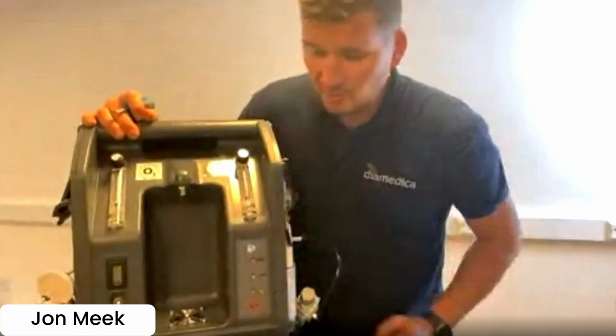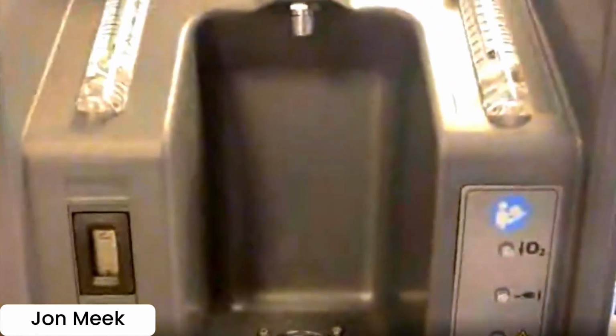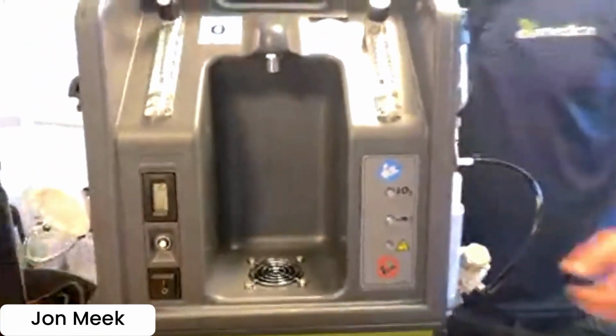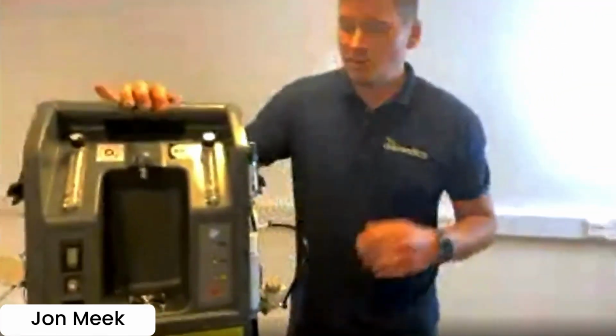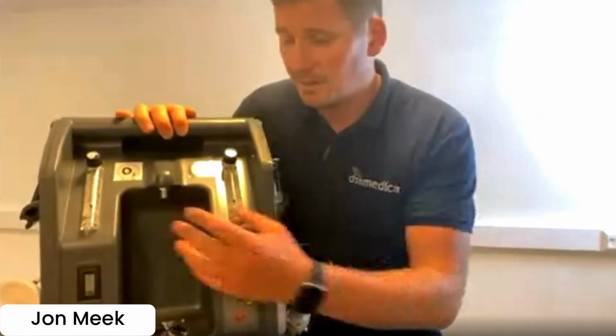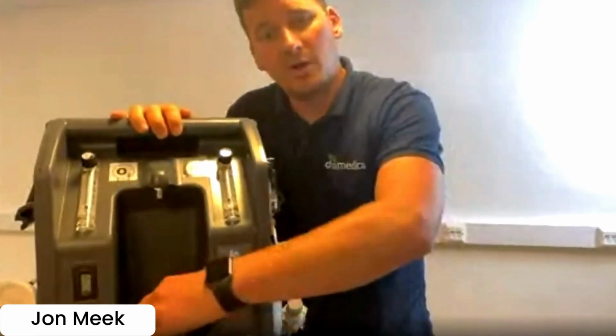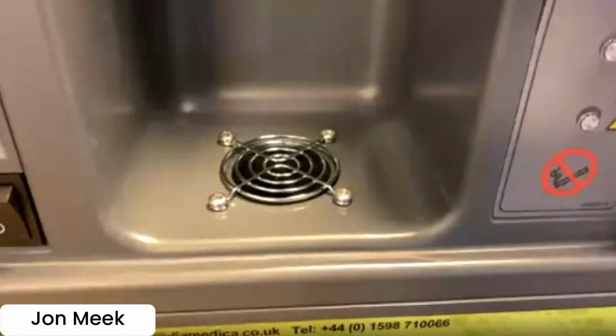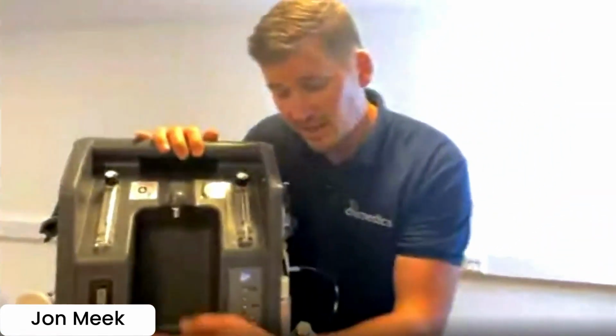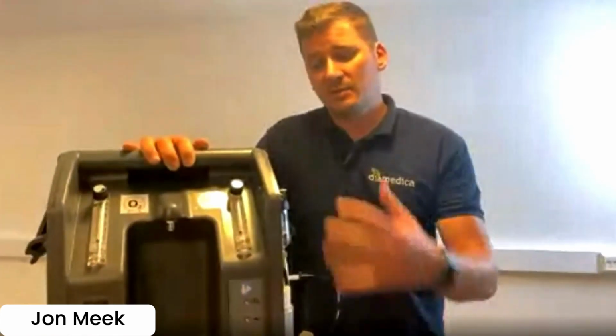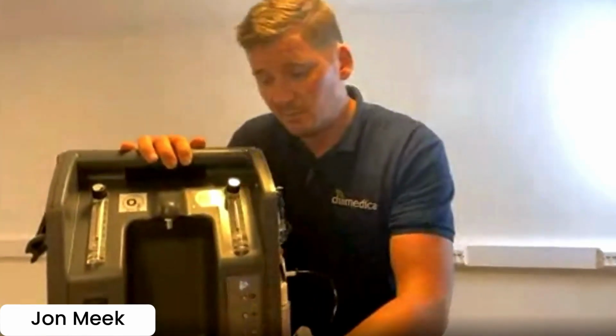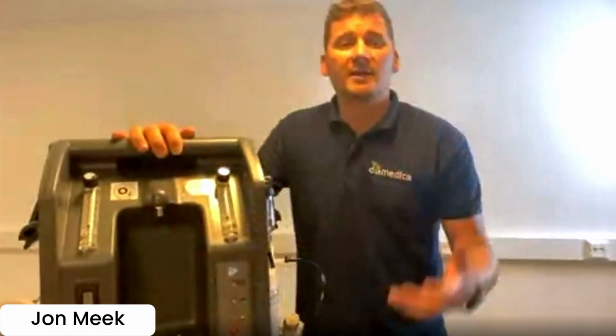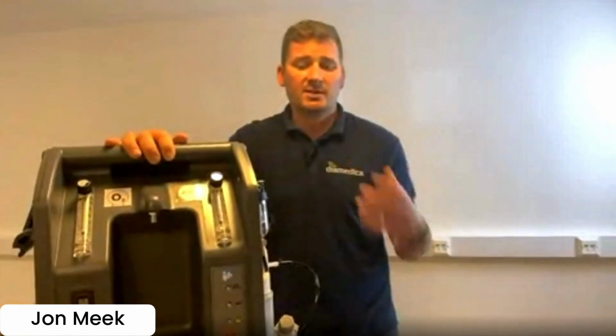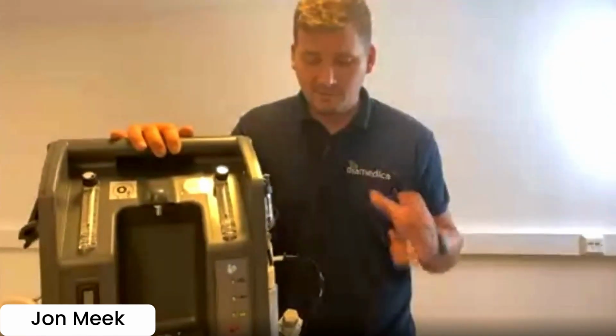We have a humidifier bottle fitted at the front, as you can see on the picture on the right, so we can humidify all of the oxygen air mixture going to the patient. We have put here a little grill with a hole going down above the compressor. So what this is doing is it's actually using its own heat generated from inside and warming the humidifier bottle. So this was the first level that we got to, where the heat was coming up and it was warming the bottle, providing extra humidification to the delivery to the patient, which is really, really important.